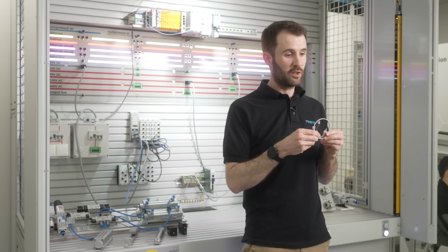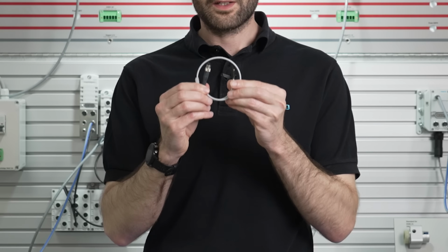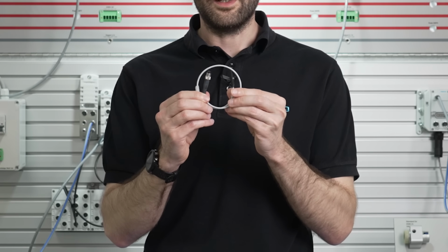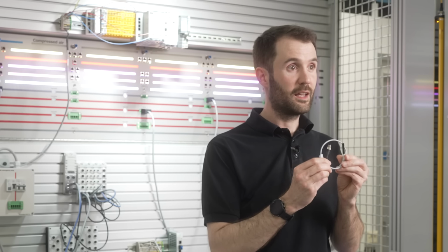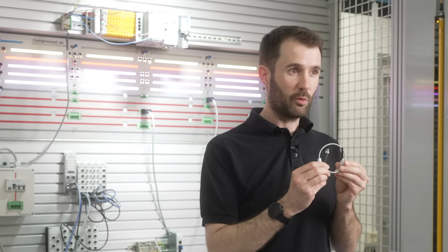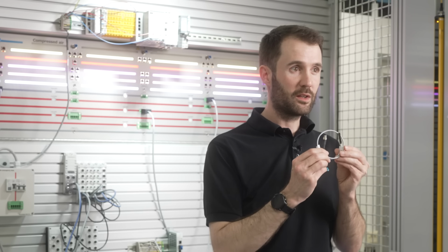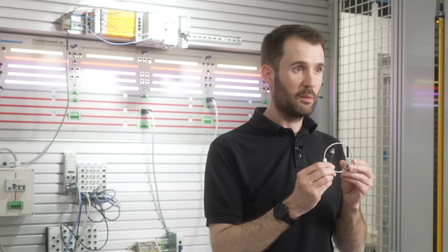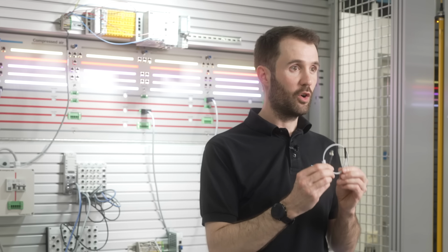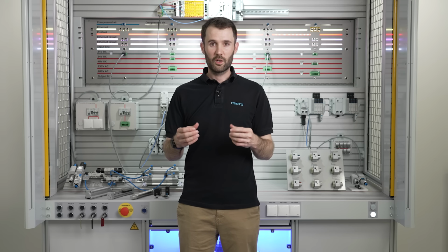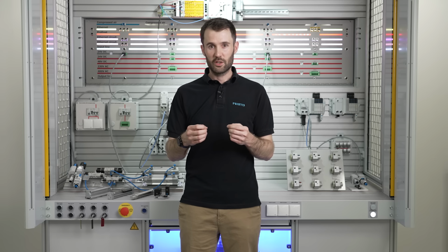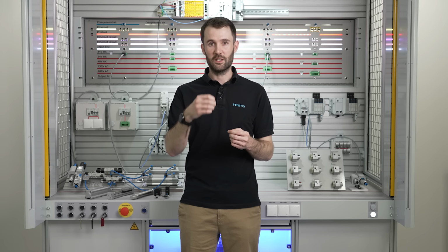And our final sensor would be a standard pneumatic proximity sensor on a cylinder. This would detect the position of our cylinder in the application, but also with the data coming back, we can start to look at the cycle time, moving from position A to B, and see the integrity of the overall platform using these sensors. So when we put all this data together, we can start to utilize the data to predict early changes in the platform.